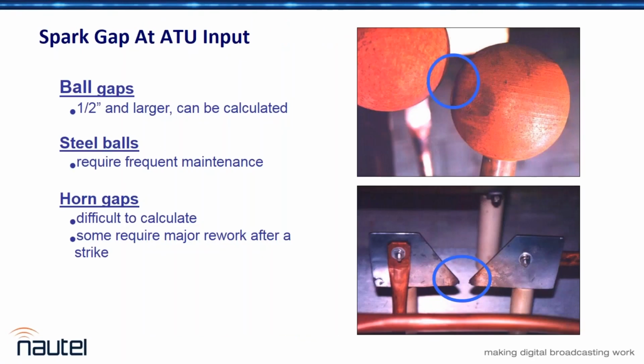Spark gaps are another thing maintenance is sometimes overlooked on. Metal gaps, especially every time they arc, get some metal migration, so they require rework, or in the case of tungsten balls, you may need to turn them on the rods. I like polished carbon balls because they don't suffer from metal migration, but in a severe strike, a polished carbon ball can vaporize, it'll just explode and disintegrate. So definitely that's a situation to watch for.